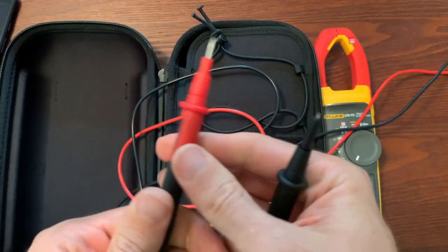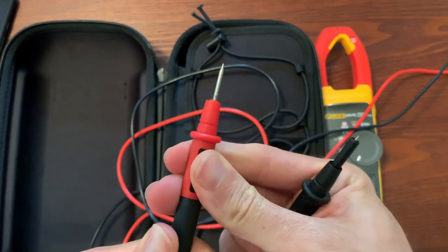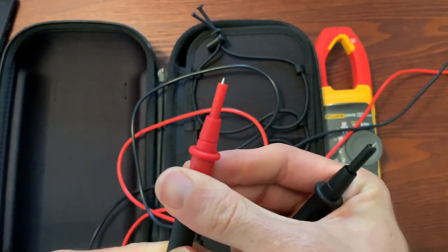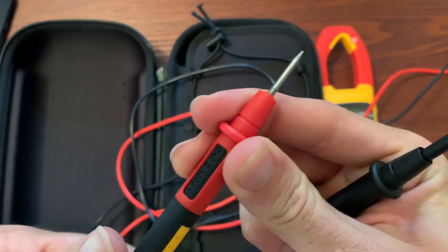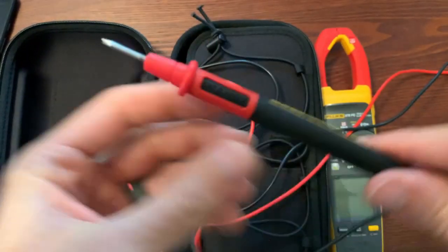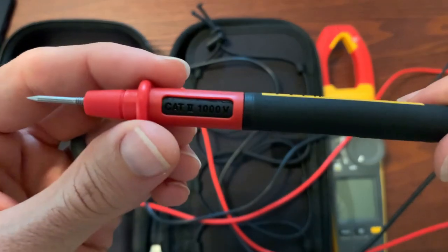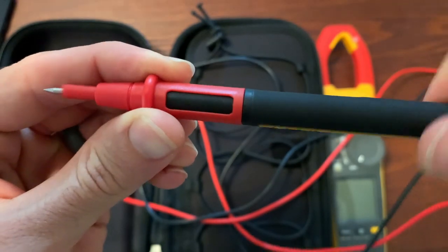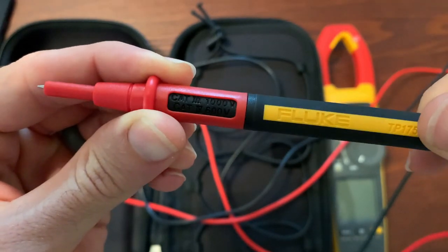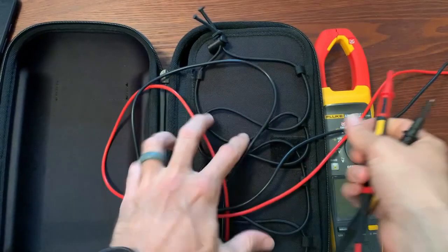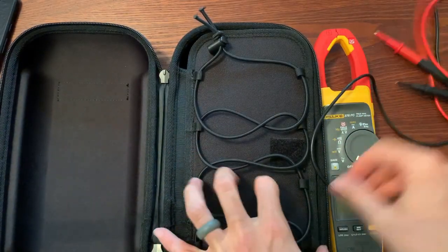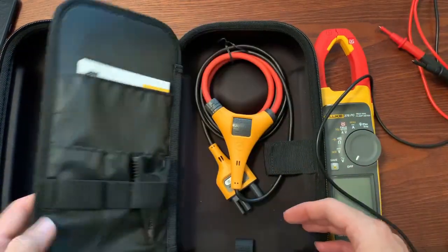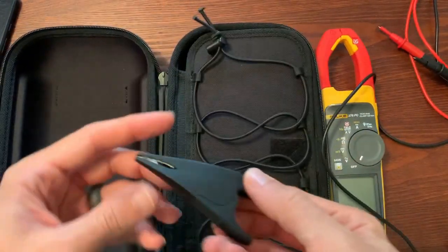The TP-175s and the TL-175s both have these twist guards which is really nice so that you have that added protection in the high voltage world. You can see as you twist them they change category ratings because cat 3 and cat 4 rated test leads can only have four millimeters of metal exposed.